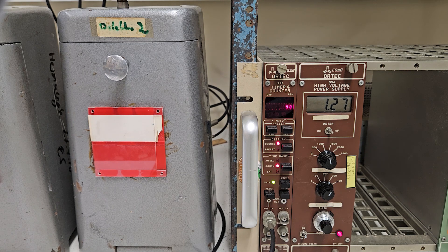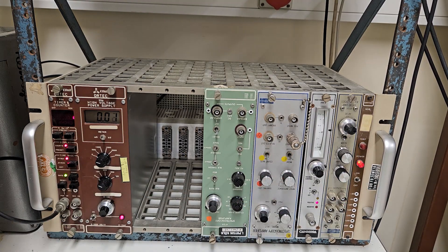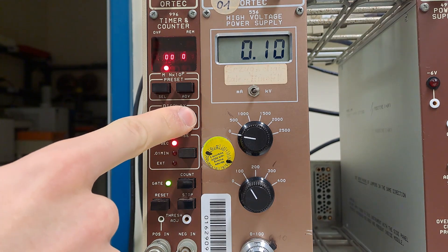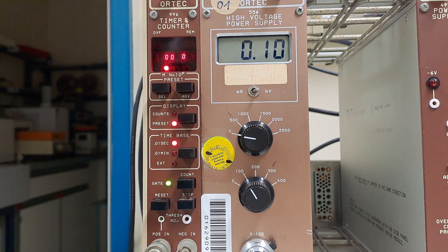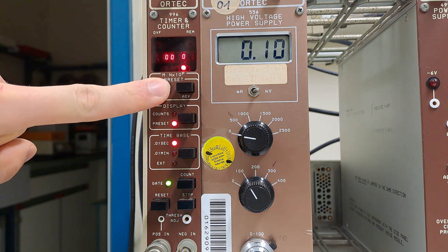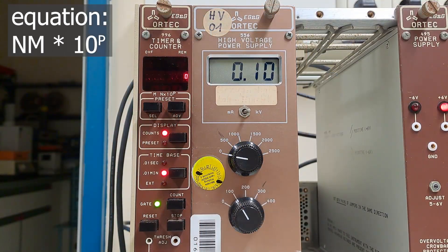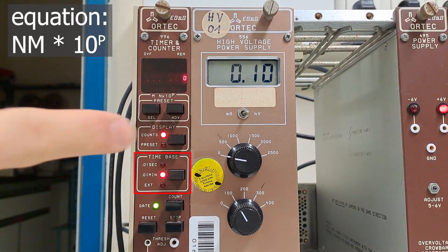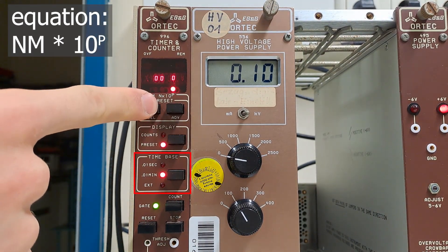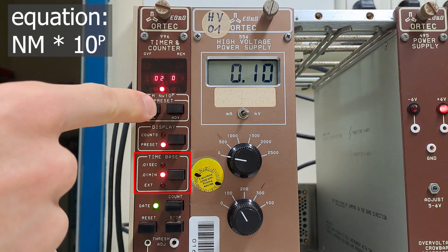First, let's get the device up and running — power on, and there also. A measurement time of two minutes is required. So we press presets, and then up there we have a display where we can see the measurement time. Below it, there is an equation that tells us what value we are currently setting: Mn times 10 to the power of p. We need two minutes, so 2 times 10 to the power of 2, since this value is given in minutes multiplied by 0.01, and so the result is two minutes.